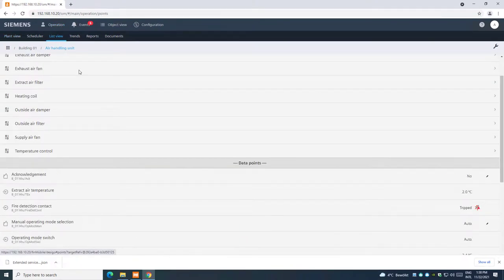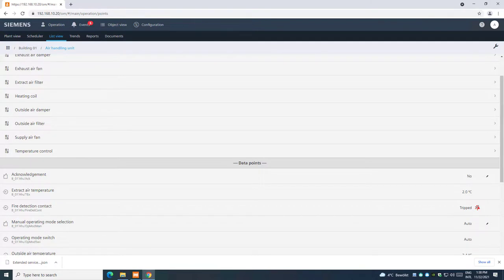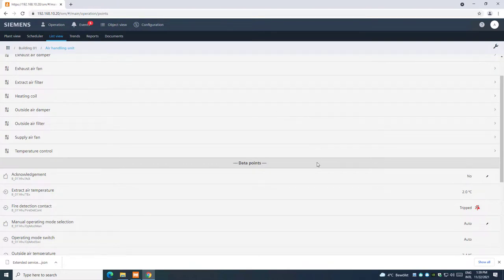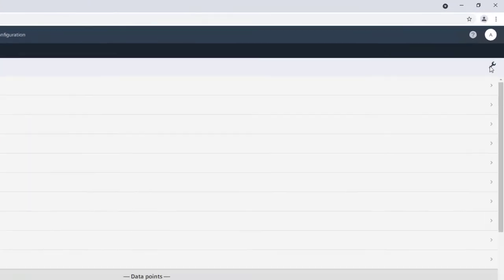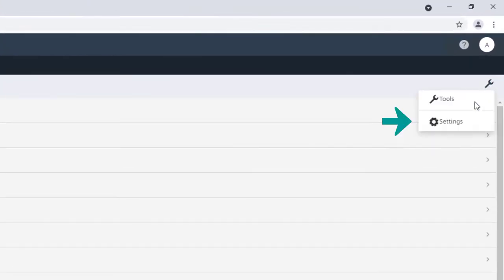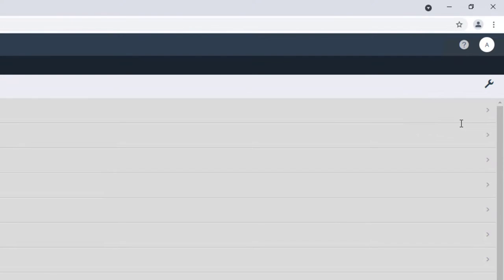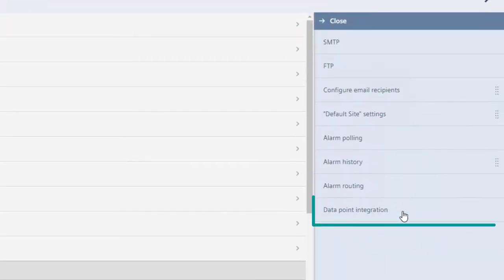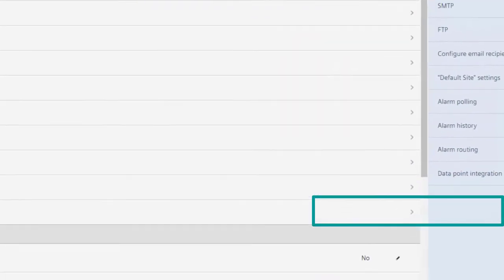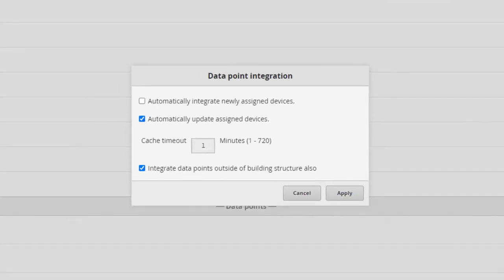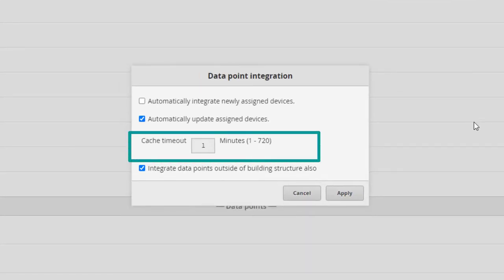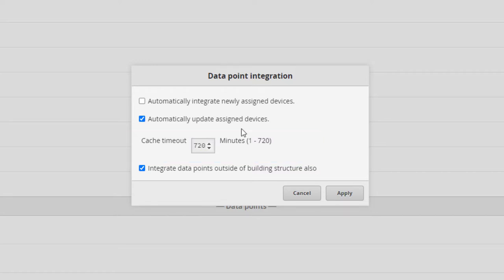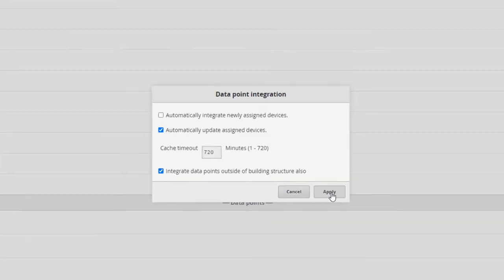As we mentioned before, the system gives the possibility to define a timeout, after which the memory busy for the cached devices can be automatically released. We can find it by clicking on Tools and Settings. Select here in the list, Data Point Integration. Define the timeout that can be extended for a maximum of 720 minutes. This feature will make the commissioning procedure easier.